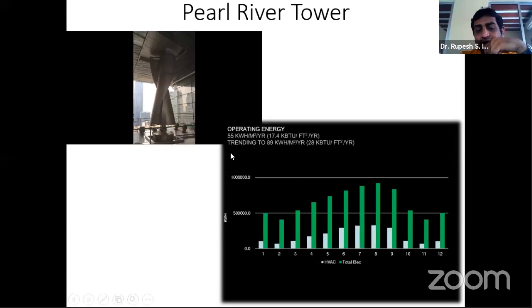On the design side, it was almost 55 kilowatt hour per meter square per year, which was targeted, and that would achieve net zero energy because that is what these wind turbines could produce. These wind turbines could only produce power equivalent to 55 into 15 lakh square feet of energy per year. But what was achieved was about 89 kilowatt hour per meter square. So I think for a building of this size, 89 kilowatt hour per meter square is quite an achievement. And buildings of this size could also aspire to achieve net zero energy.